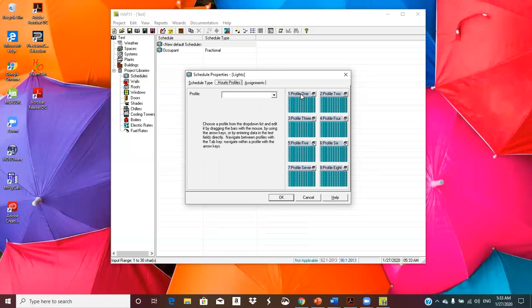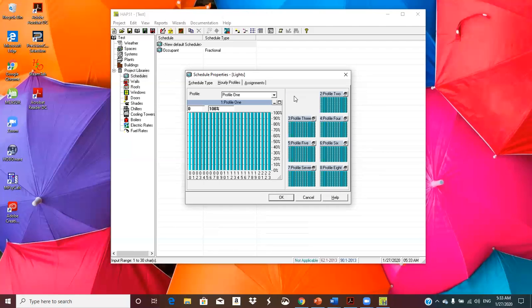And we'll say we're just going to leave, let's say this is, again, weekday. And we'll go 0 through 6. And we just leave, say, 10% of the lights on at night. And then we'll say 21 through 23. I'm just trying to get something in here. People are still cleaning, but they got most of them off.